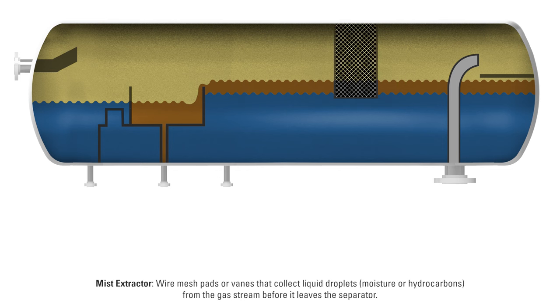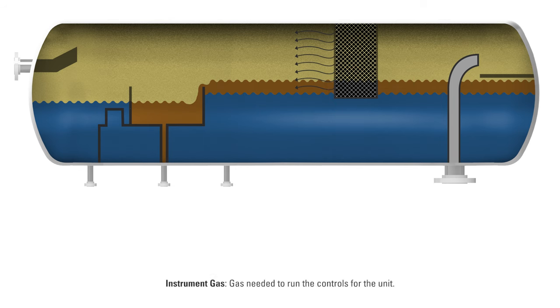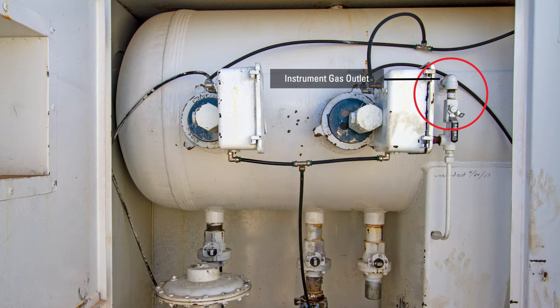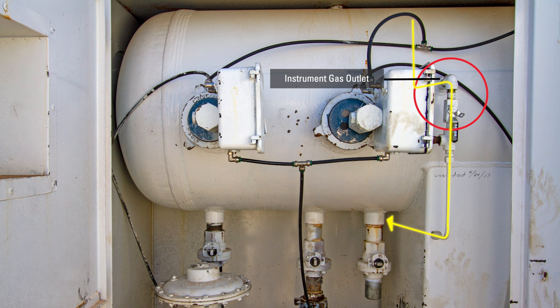There's a mist extractor inside the vessel located approximately here. The mist extractor extends just below the liquid level, which forces the flow of gas through the extractor. Instrument gas refers to the gas needed to run the controls for the unit. This half-inch line goes in and turns up, and that's where you'll get the highest, driest gas possible, which is what you want for instrument gas.